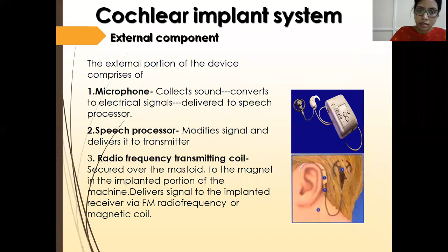So your internal or implanted part of your cochlear implant consists of a receiver stimulator and a multi-channel electrode array. See, don't get confused between a microphone and a receiver. Receiver, the patient receives the sound, whereas microphone picks up the sound from outside. So microphone, processor and a transmitting coil are your external component, whereas your internal component consists of your receiver and an electrode array. So this receiver stimulator, it has a magnet and an antenna.